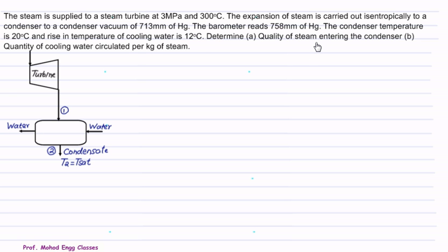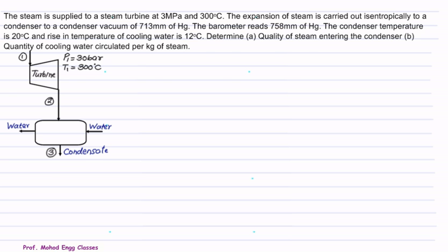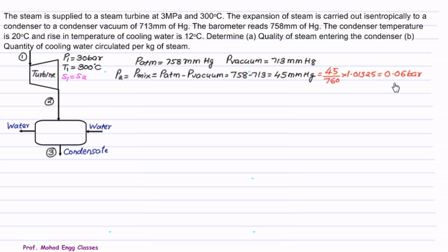We want to find the quality (dryness fraction) of steam at the condenser inlet and the quantity of cooling water per kg of steam. The absolute pressure at the condenser is P_mix = P_atmospheric − P_vacuum = 758 − 713 = 45 mm of Hg. Converting to bar: 45/760 × 1.01325 ≈ 0.06 bar. The temperature rise of cooling water is 12°C and condensate temperature is 20°C.